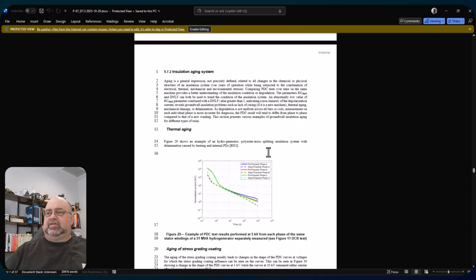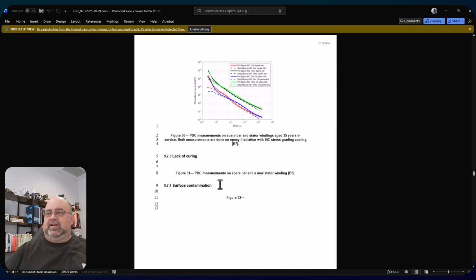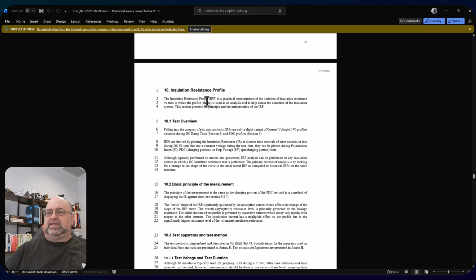Here we go - insulation aging, lack of curing, insulation resistance profile. It's a graphical representation of insulation resistance versus time, in which the shape is used as the analysis tool. Why is this important? Well, because as we'll discuss with 43, insulation resistance testing by itself is not meant to condemn or pass a motor. I've seen some bad information showing up on places like LinkedIn, where people go onto ChatGPT or equivalent, capture wrong information, and present it, trying to show themselves as experts. Very, very sad. But here's the test.